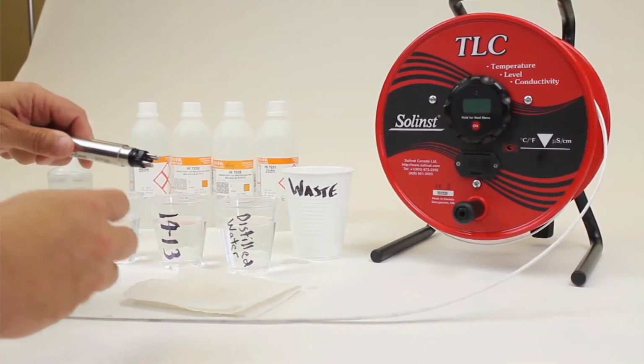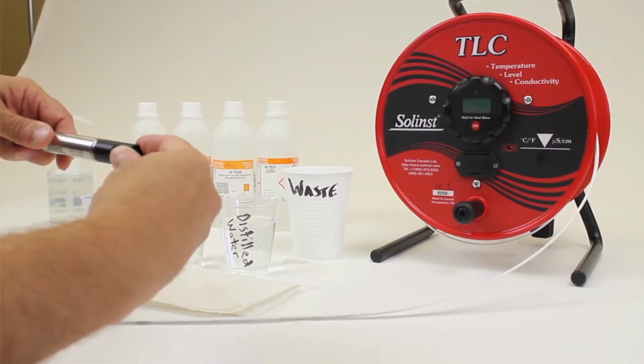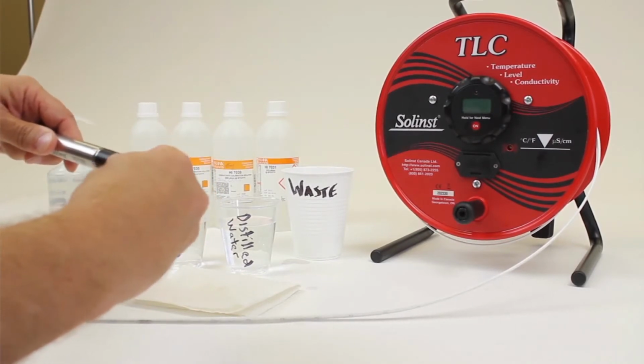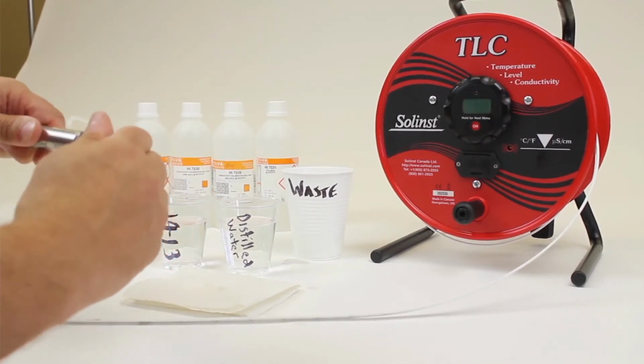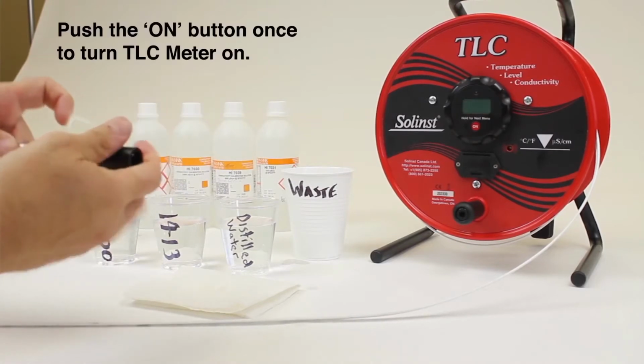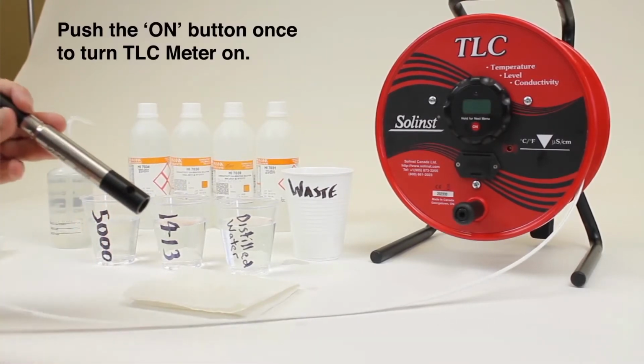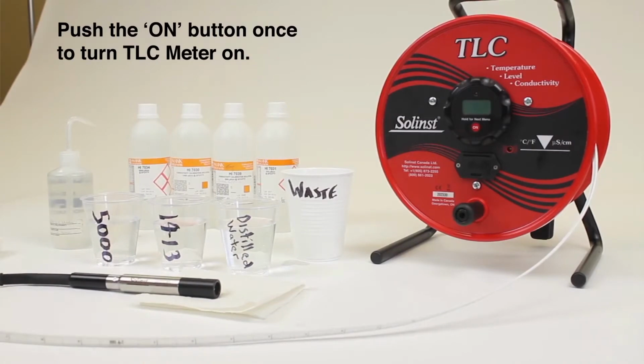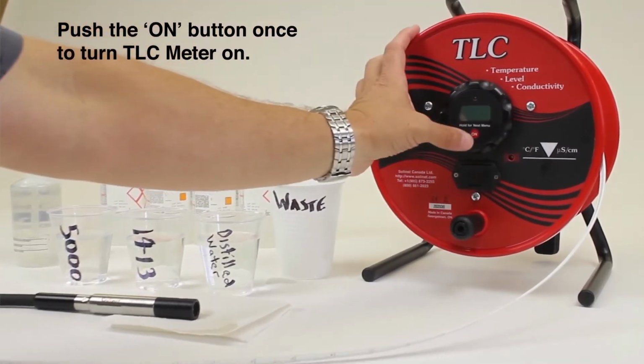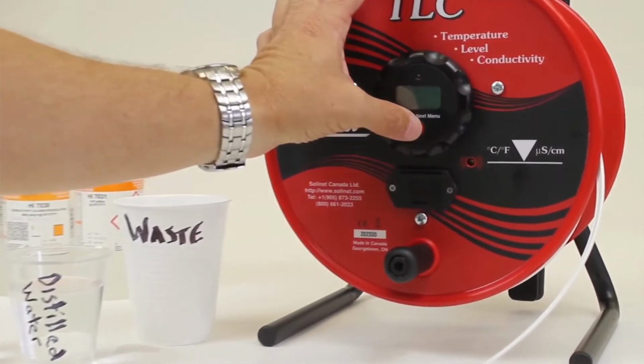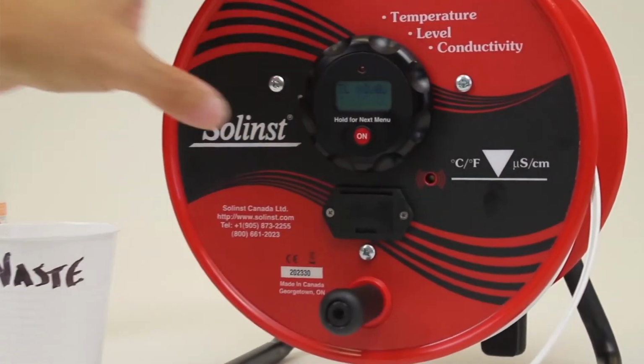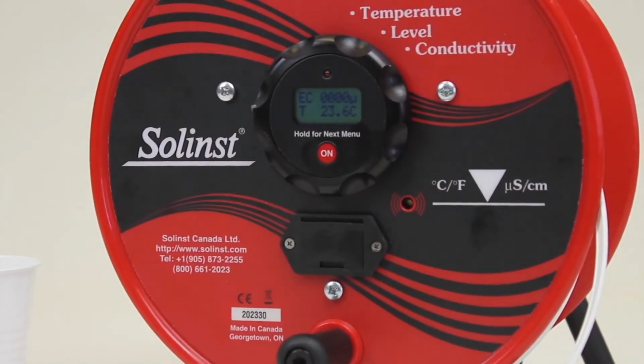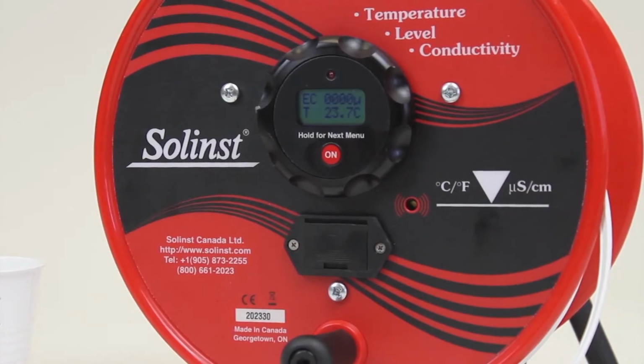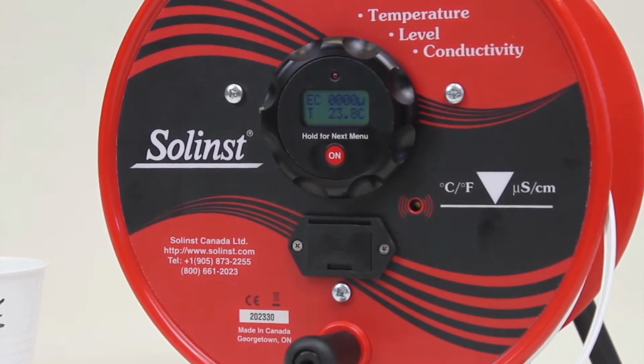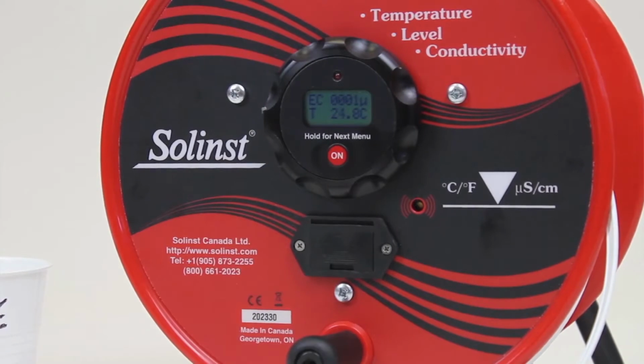I'm just going to inspect the O-ring, that's in good shape. Slide on the probe shroud. Turn it slightly until I feel that the notch has lined up. Lock it in place. So I'm ready to start the calibration session. The first thing is I'm going to push the on button once to turn it on, and it comes to the main screen, which shows the conductivity and temperature right now in air. Everything here has been sitting out for quite some time, so it's all at the same temperature.